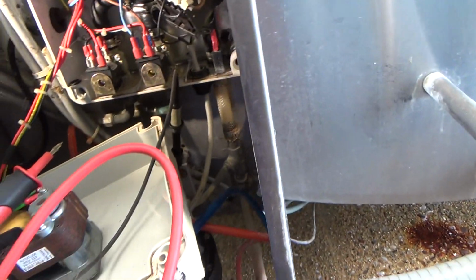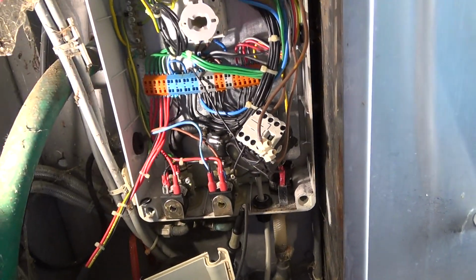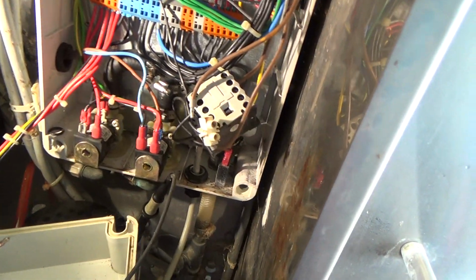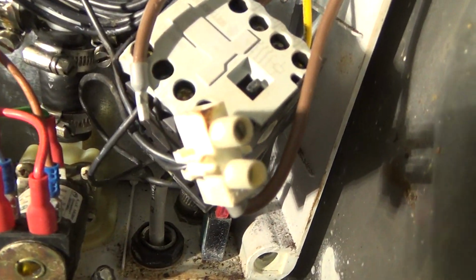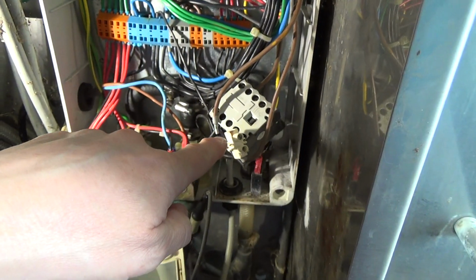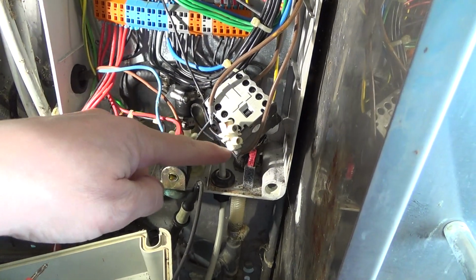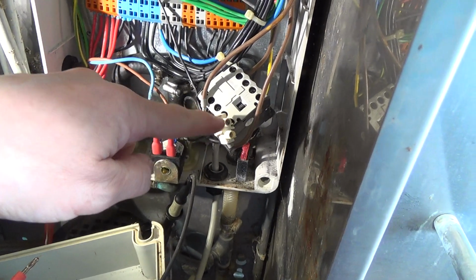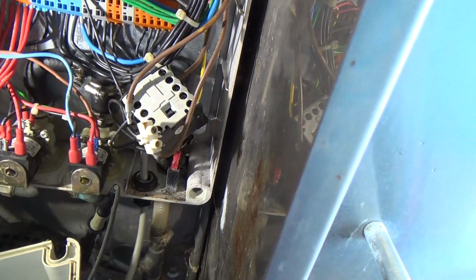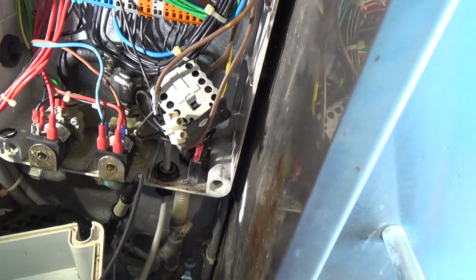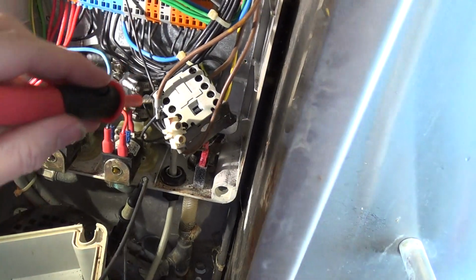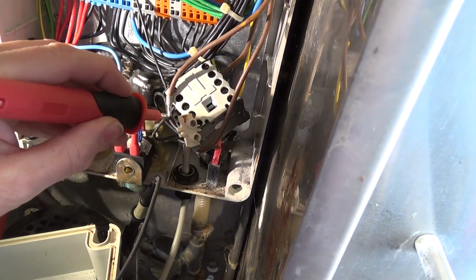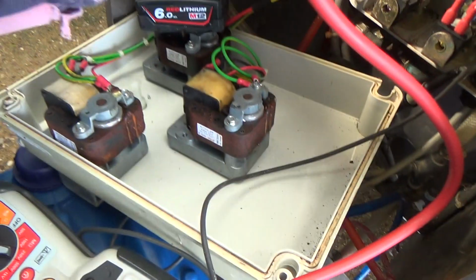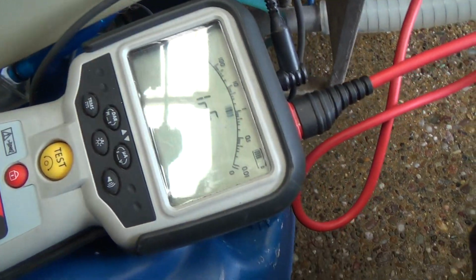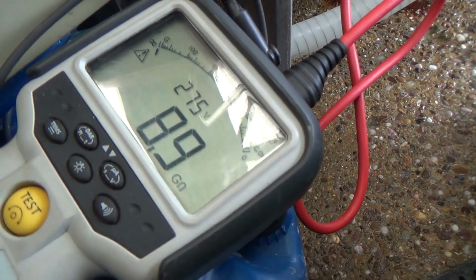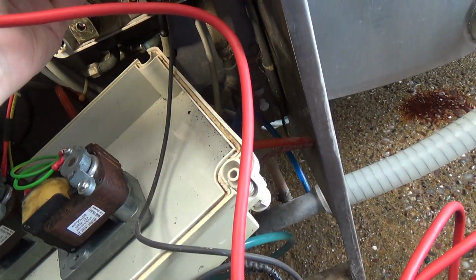Okay, what we could do is split it here. Let's do that. Okay, just something to be careful of. That rusty mark there, that's enough to create a short to knock a trip out, because if that rusty line went inside, the current would travel through the rust if it was touching a piece of metal. So it doesn't even have to be anything major that will make something trip. Right, so we've broken that into two. So if I put the test lead on there, let's try it up here, it'll be easier. So we're now gigaohms, so that wire is good.